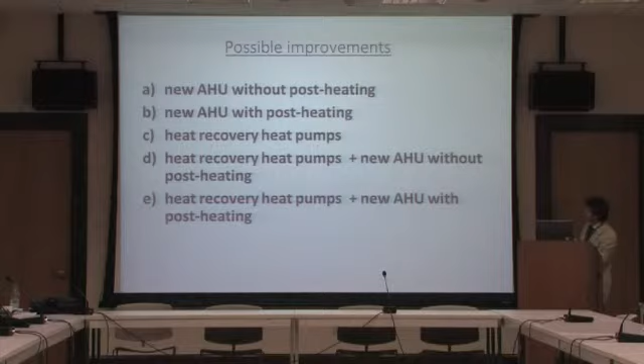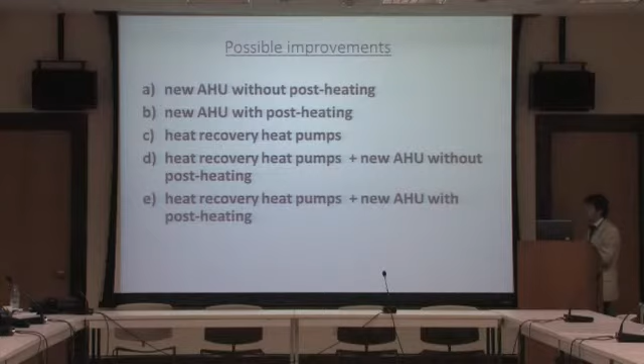Then the third case was the case of heat recovery heat pumps. Heat recovery means that at the same time, on the condenser, you can release heat, and on the evaporator, you can cool the system. So that means that you have a system where you are only consuming electricity, and you have a double effect, heating and cooling. And of course, this is possible when you have simultaneous heating and cooling loads. Then we had the combination of the heat recovery heat pump with the 2 air handling units, without and with post heating.